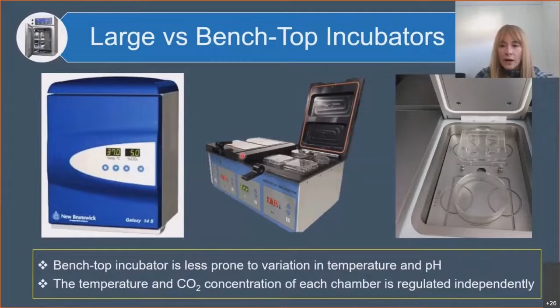On the other hand, benchtop incubators are less prone to variation in temperature and pH. We can see that in each chamber, only a few dishes can fit here. So actually this is an advantage because the temperature and CO2 concentration of each chamber is regulated independently. So whenever we open the door, the rest of the dishes are not affected.